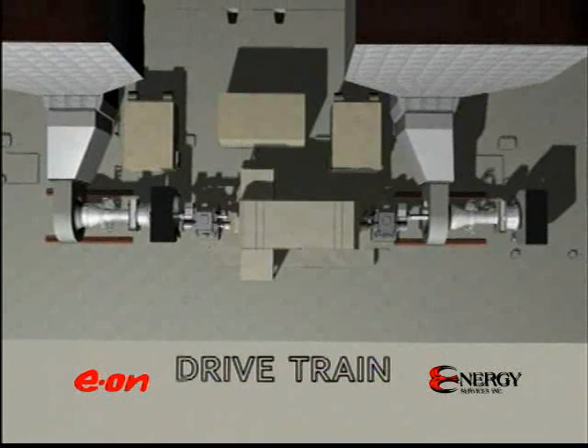Now let's take a bird's eye view so that we can see the whole drivetrain. We'll start at the left with the Unit 1 gas turbine. Its flex coupling is driven from the intake, or cold end drive end. The flex coupling transmits power to the Unit 1 speed reduction gearbox. The Unit 1 and Unit 2 gearboxes also incorporate clutch and brake systems that allow either gas turbine to drive the generator individually or together for full power.